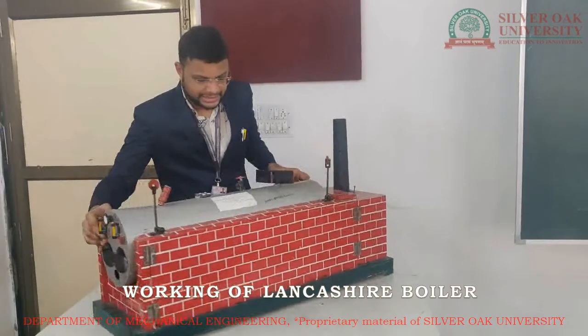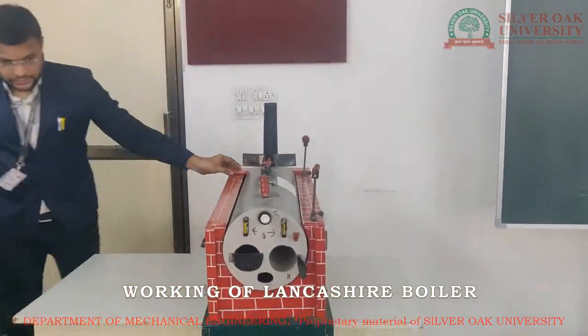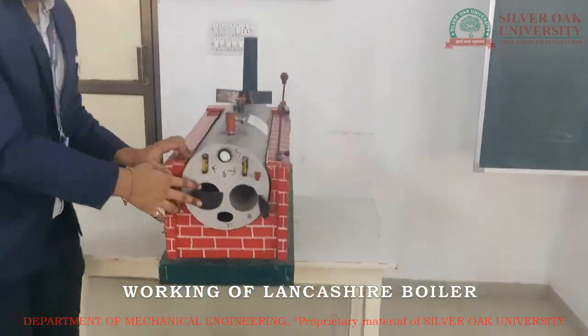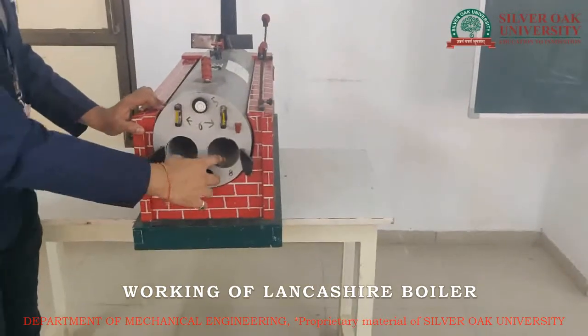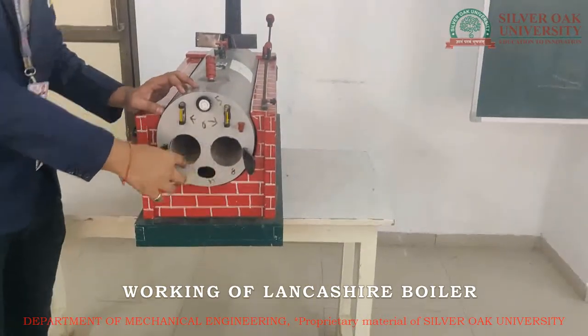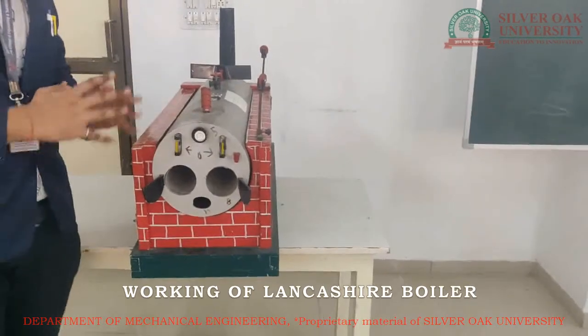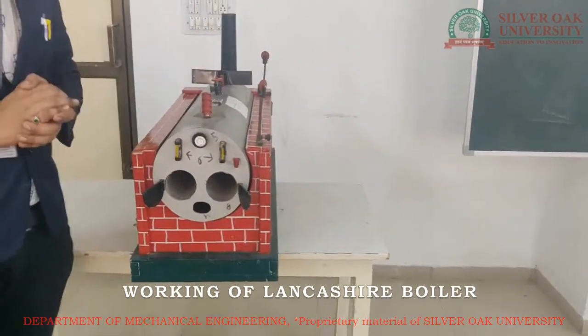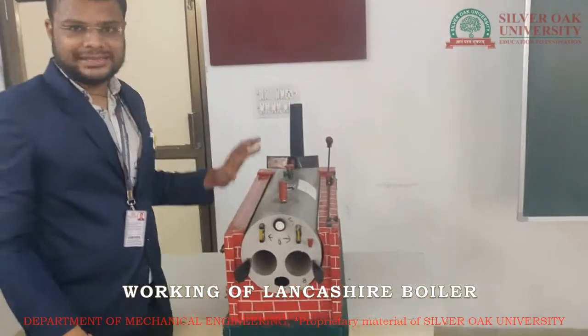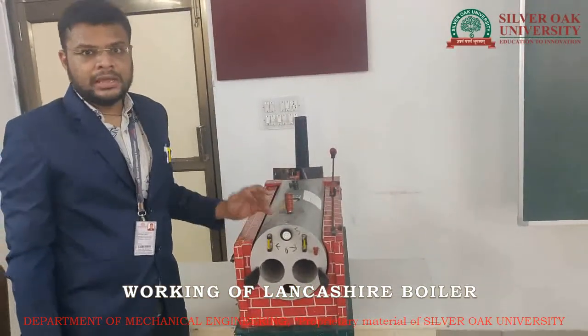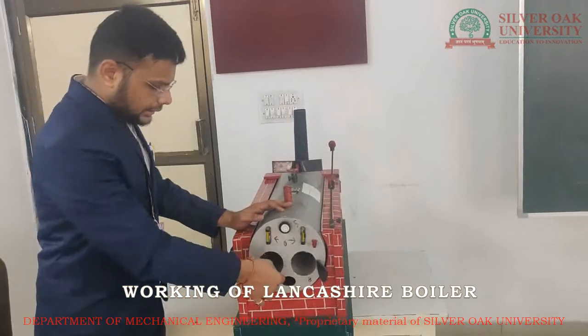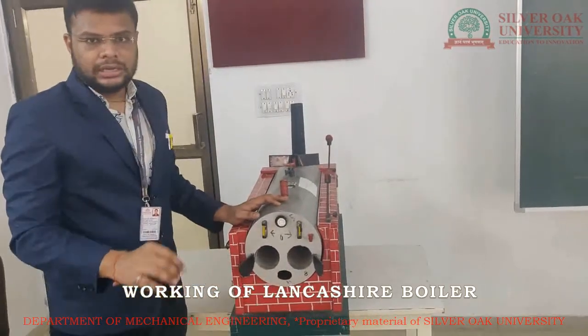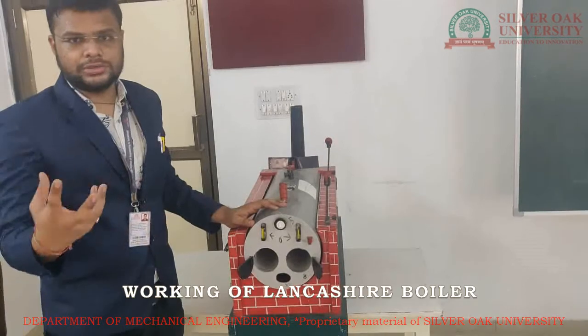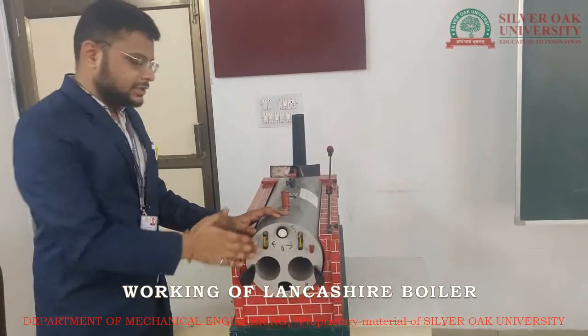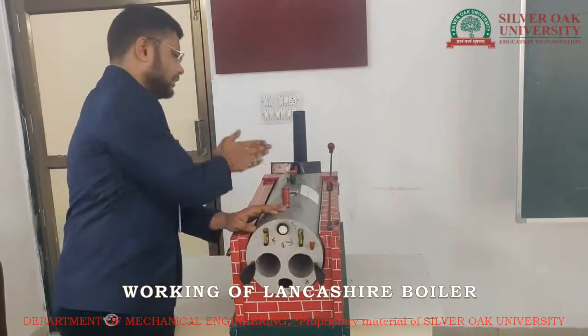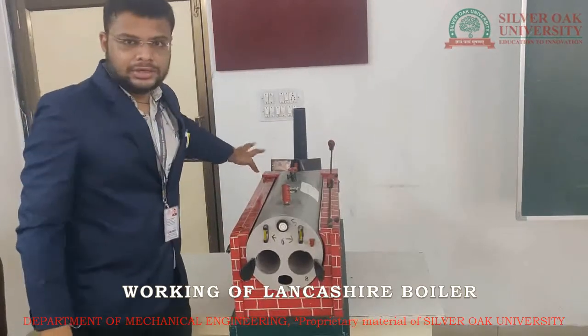Now here you can see we have two fire tubes. The entrance portion of the fire tube contains the grate area on which the coal is introduced. Likewise, as in other types of boiler, the water is fed inside the water drum. After filling the water drum, coal is introduced at the grate area, and due to the burning of the coal, it produces hot flue gases. These hot flue gases are circulated entirely inside the tubes.